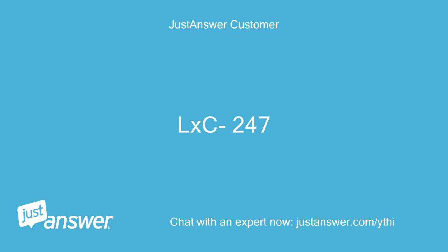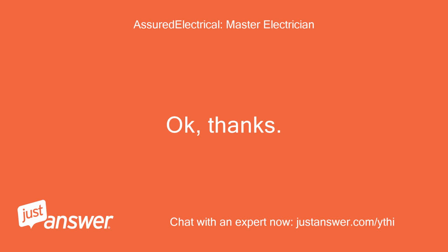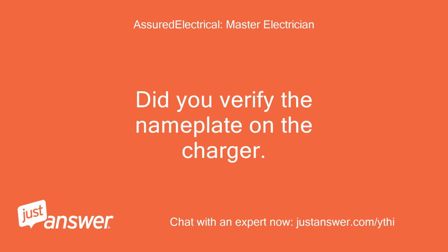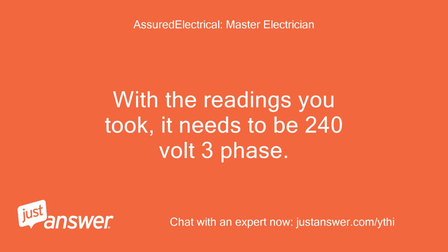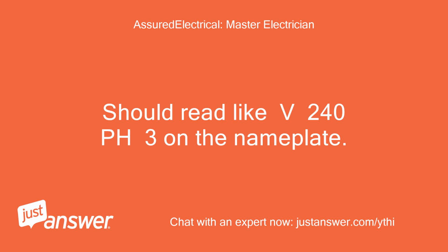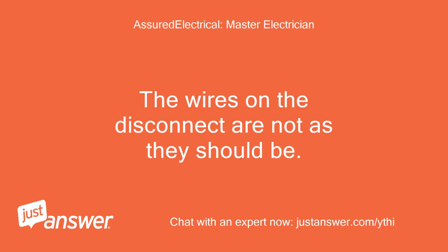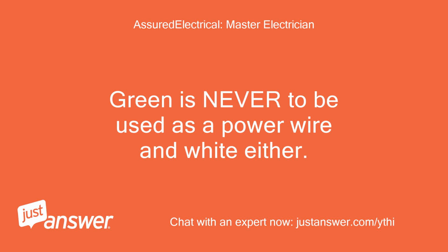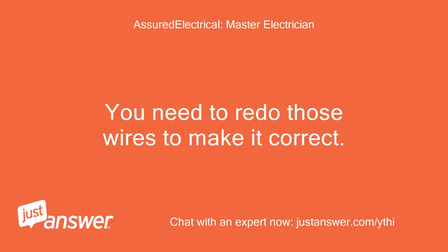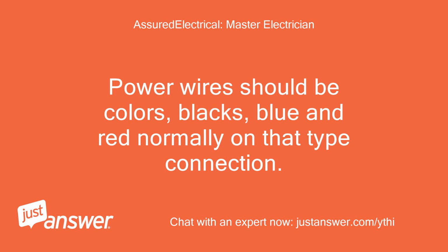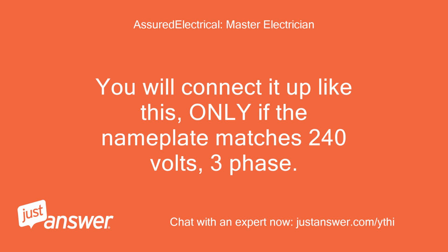LXC 247. CXR 247. LXR 247. Okay, thanks. Did you verify the nameplate on the charger? With the readings you took, it needs to be 240 volt 3-phase. Should read like V240pH3 on the nameplate. The wires on the disconnect are not as they should be. Green is never to be used as a power wire and white either. You need to redo those wires to make it correct. Power wires should be colors, blacks, blue and red normally on that type connection. You will connect it up like this, only if the nameplate matches 240 volts, 3-phase.